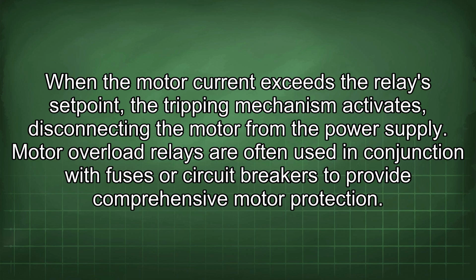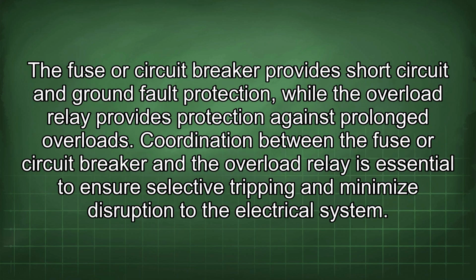Motor overload relays are often used in conjunction with fuses or circuit breakers to provide comprehensive motor protection. The fuse or circuit breaker provides short circuit and ground fault protection, while the overload relay provides protection against prolonged overloads. Coordination between the fuse or circuit breaker and the overload relay is essential to ensure selective tripping and minimize disruption to the electrical system.